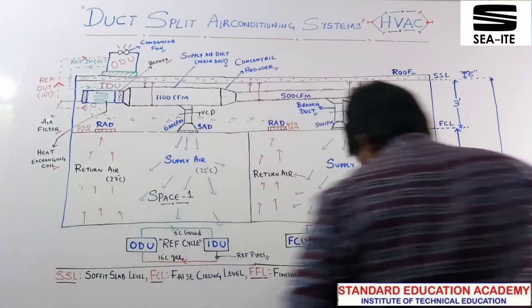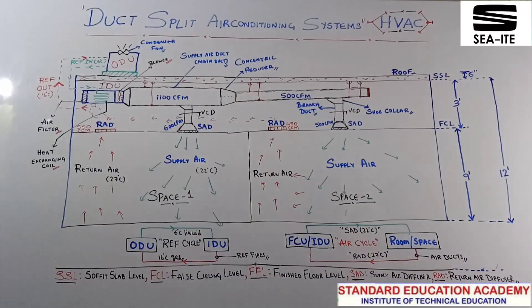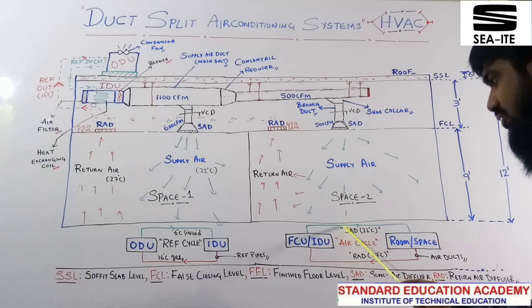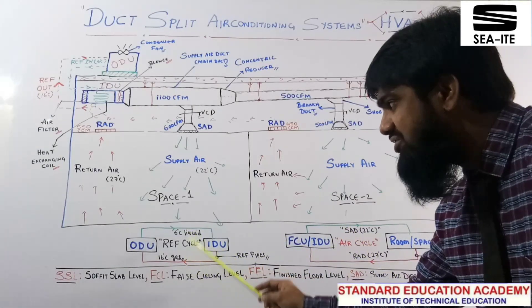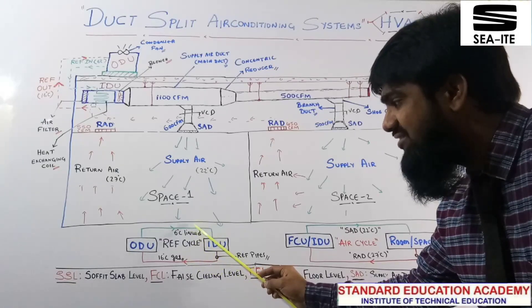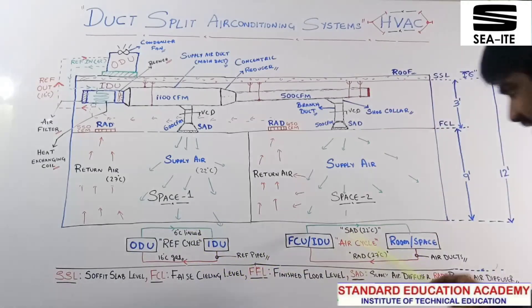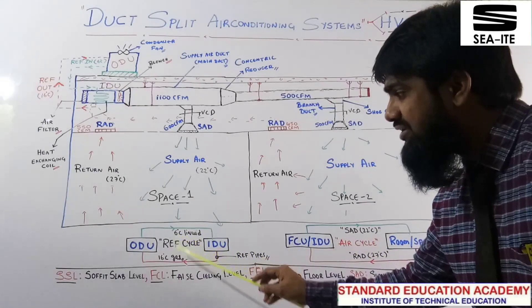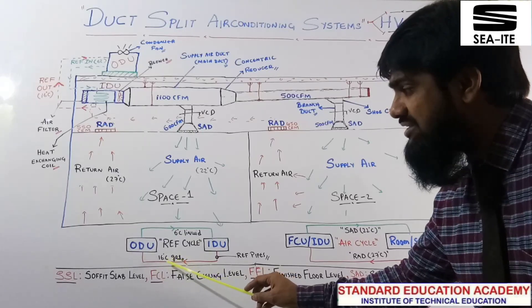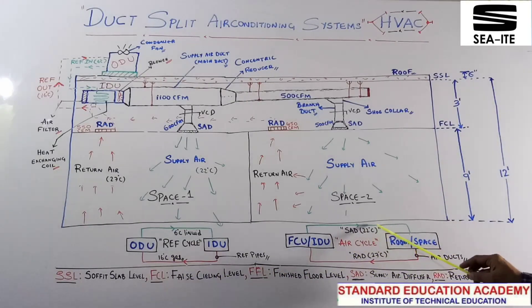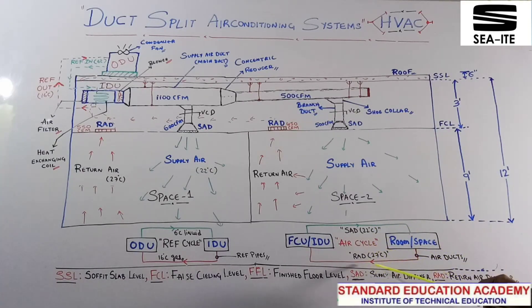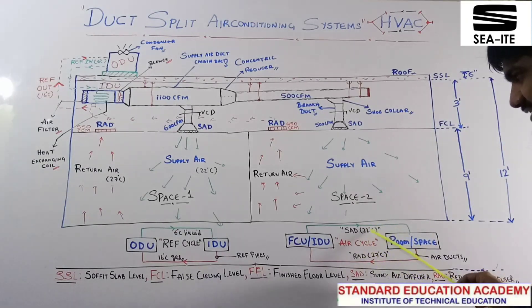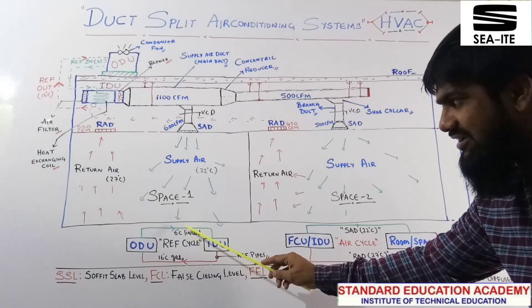Then let's come to our air cycle. The air cycle is all about ducts; the refrigeration cycle is all about refrigerant pipes. Keep it in mind — the red and green colors shown are the refrigerant pipes, while in the air cycle diagram the colors represent ducts. Green is for low temperature supply air at 22 degree Celsius, and red is for return air at high temperature, 27 degree Celsius.